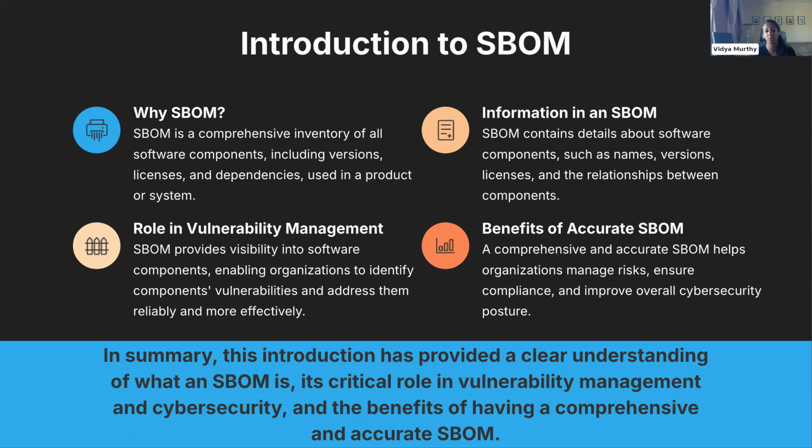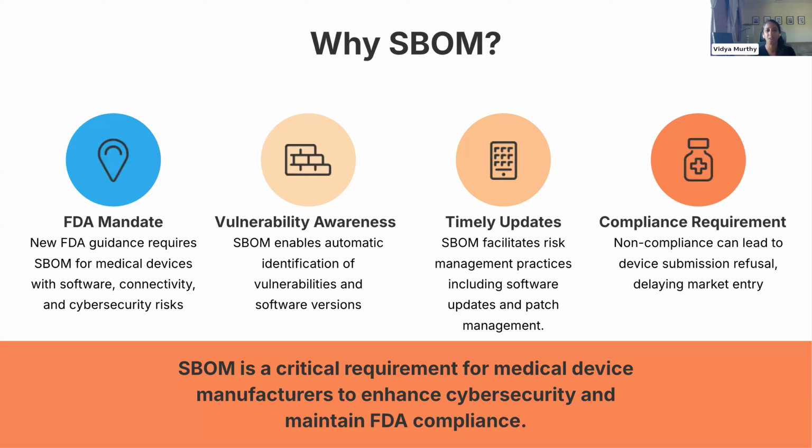Basically, we'll work through all of this in the context of being a device manufacturer that has to submit to the FDA, because there are clear requirements that we all face. So why SBOM? The first one, FDA mandate. The FDA has a requirement that says you must submit a software bill of materials for devices with software, connectivity, and security risks. This includes customers also. So a lot of hospitals are asking for the same type of content as what is being provided to the FDA. Customers meaning health systems or consumers of devices that often want an SBOM.